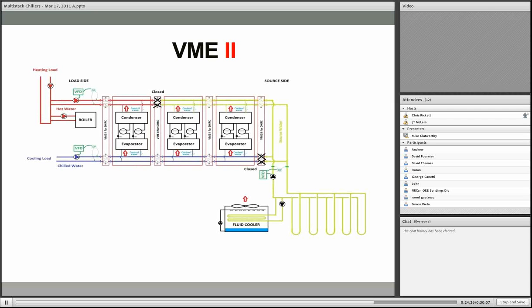And then one more scenario, 2 in cooling, 1 in heating. So I've got 1 module rejecting to the hot water loop, 2 in cooling, and then nothing happening here. And as I mentioned before, fluid coolers can be integrated into this, especially if let's say you've got an existing geothermal well field that's been proven over time not to be quite large enough, then you can augment it with a fluid cooler.